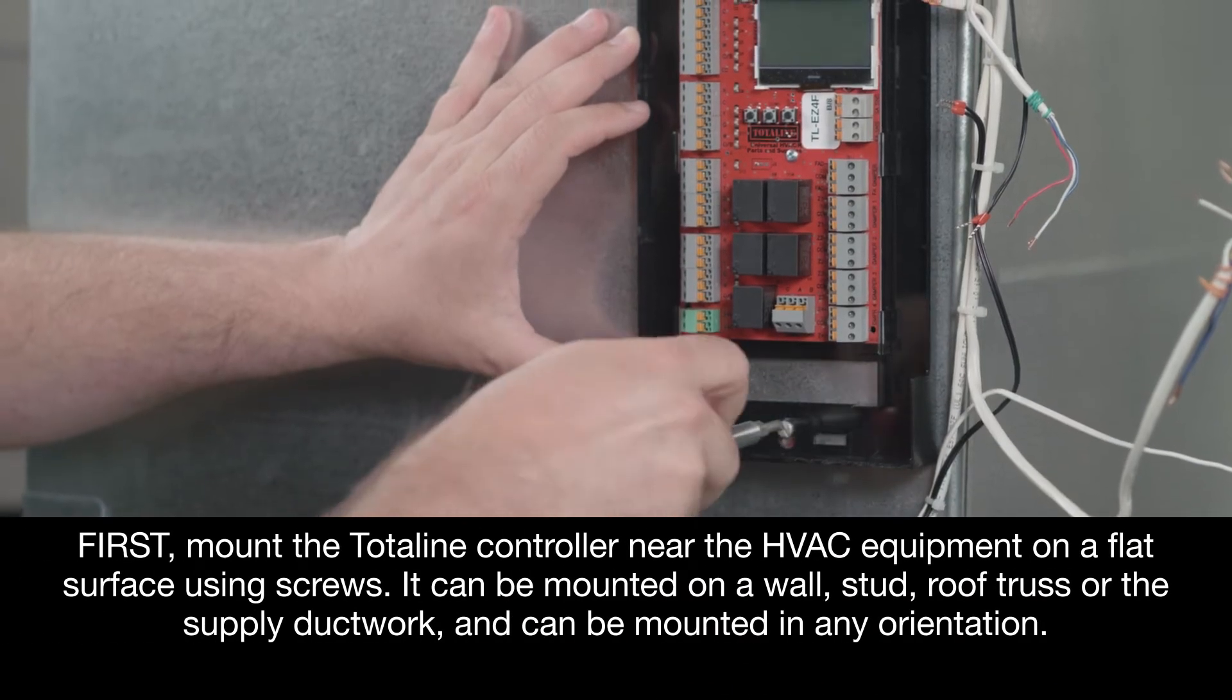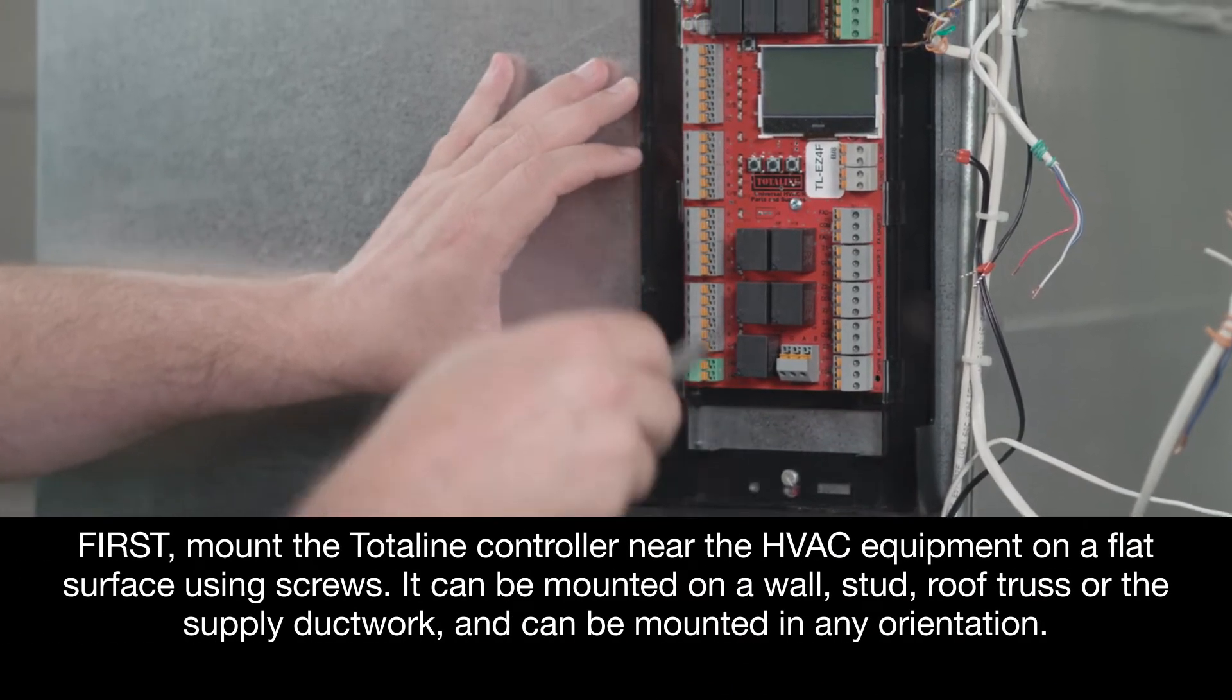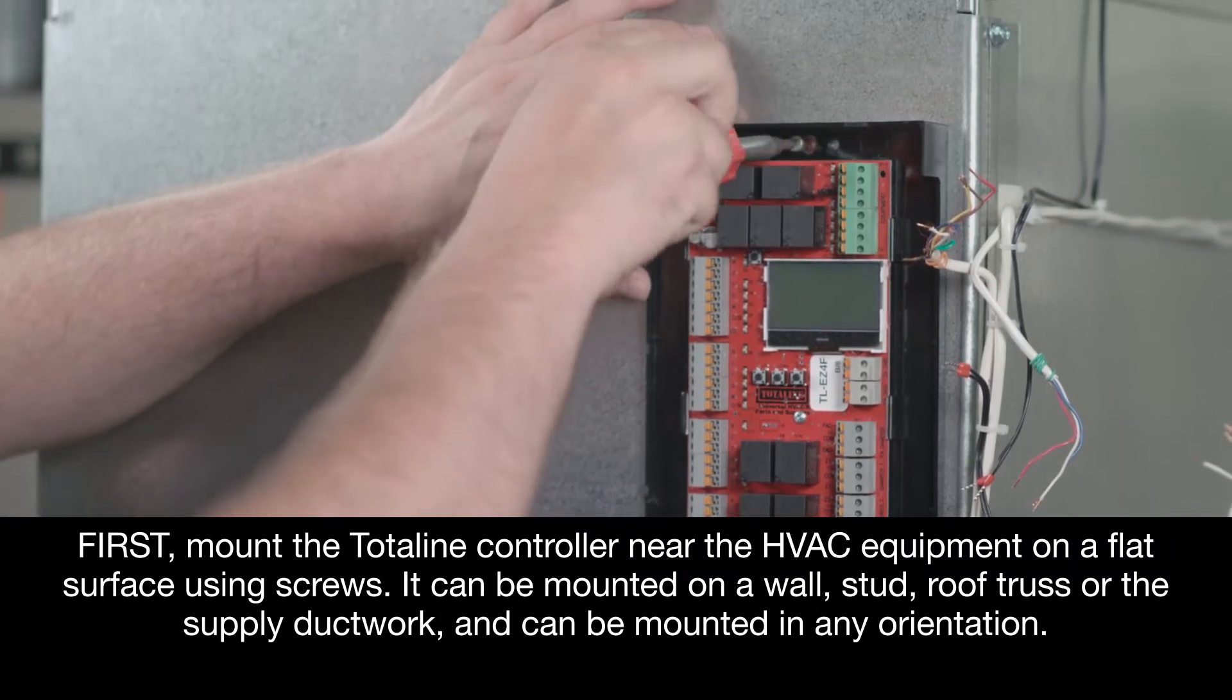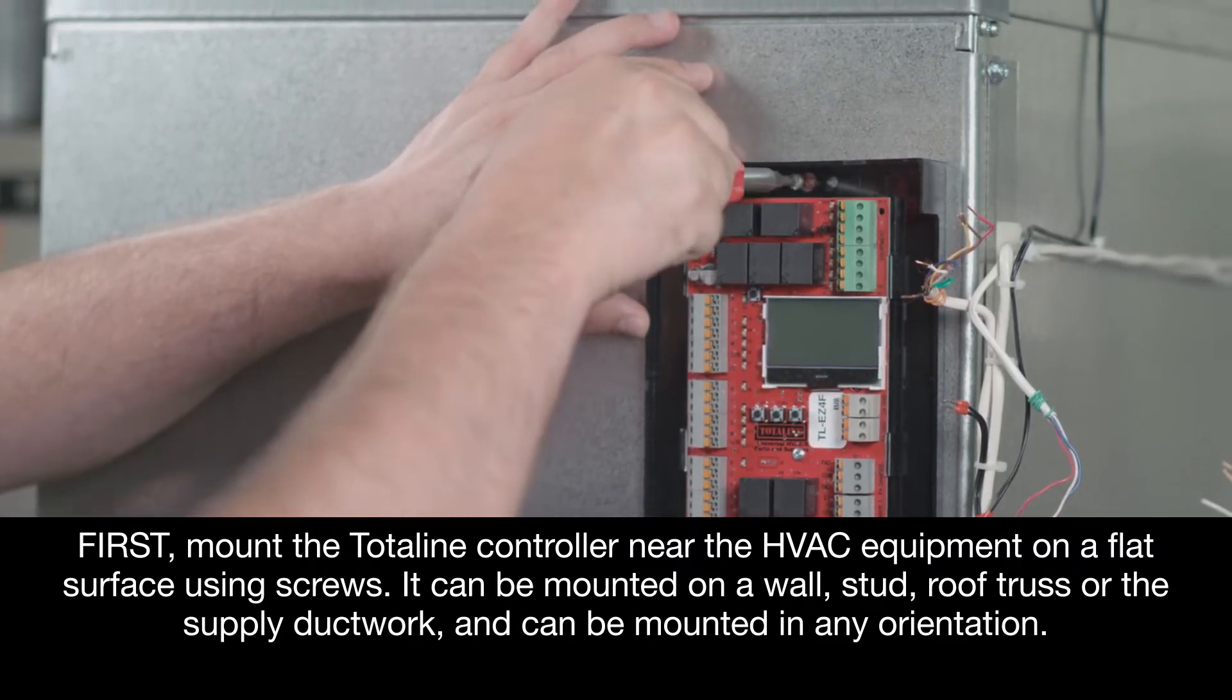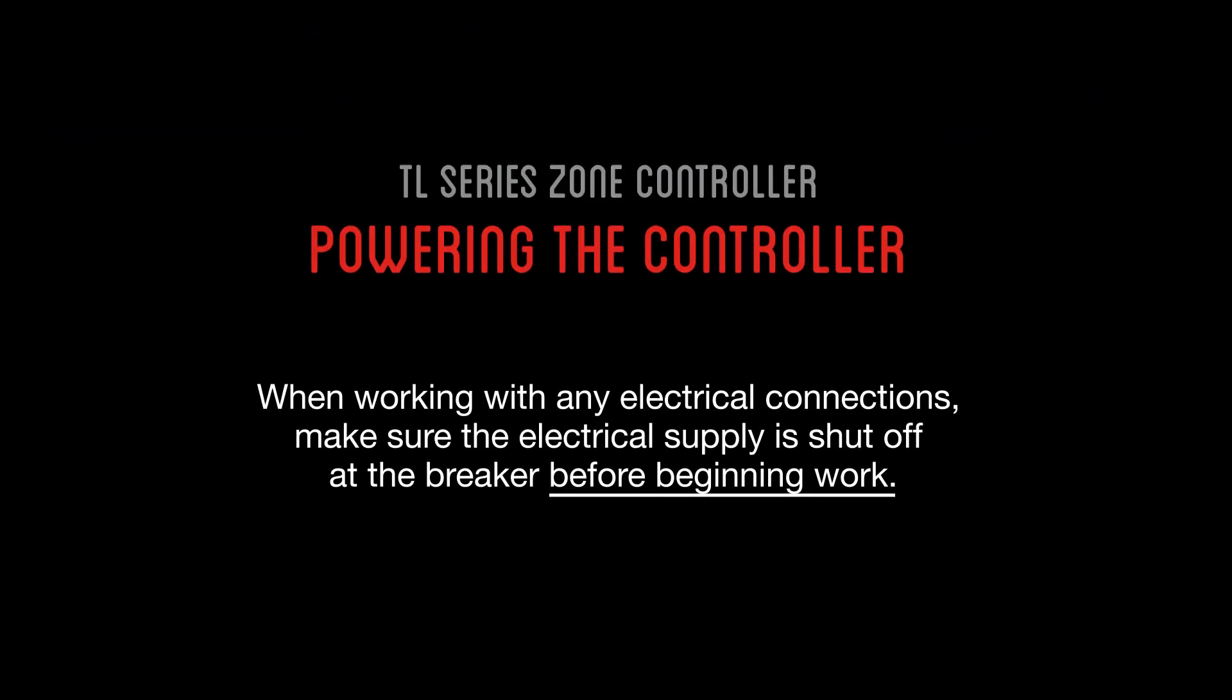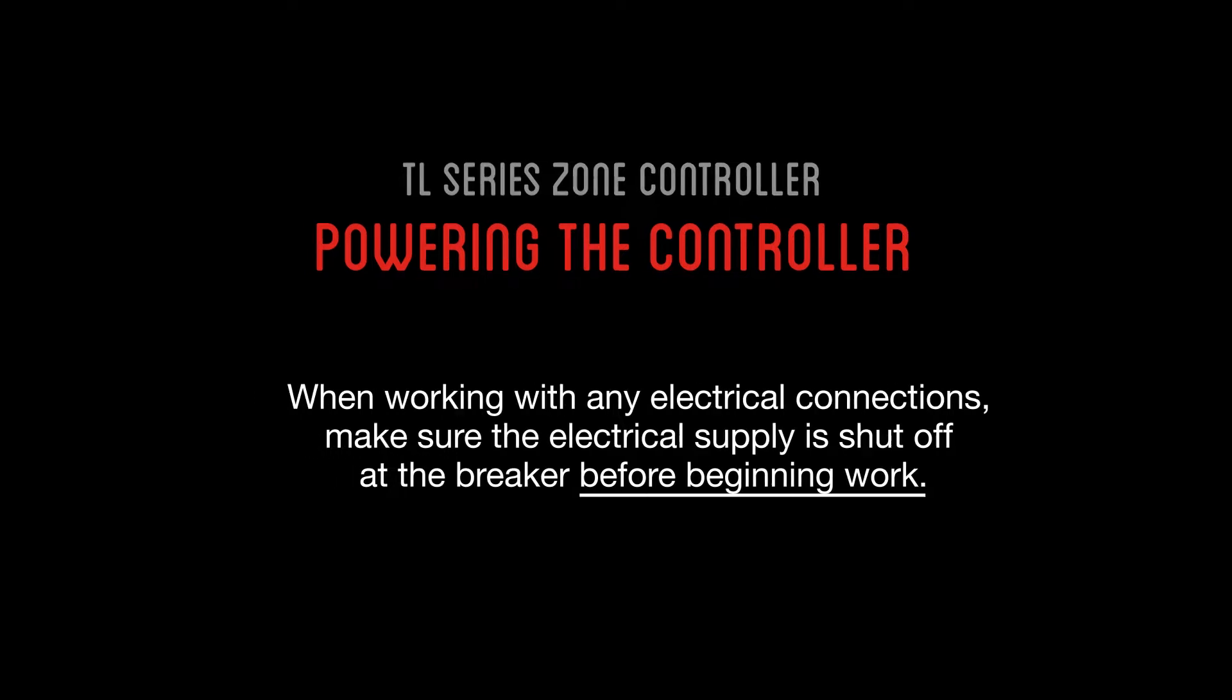First, mount the Totaline controller near the HVAC equipment on a flat surface using screws. It can be mounted on a wall, stud, roof truss, or the supply ductwork and can be mounted in any orientation. When working with any electrical connections, please make sure the electrical supply is shut off at the breaker before beginning work.